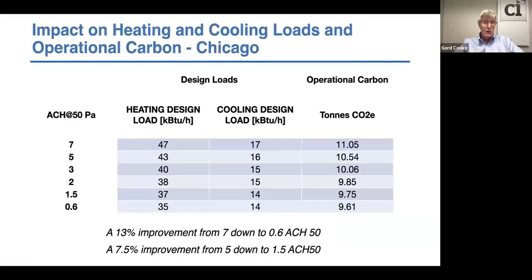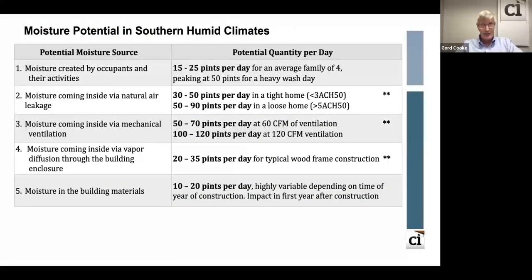But I'm just highlighting here the Chicago market, the design heat loads. When you go from, say, 3 air changes at 40,000 BTUs, that's on the left-hand side, down to 1.5, a small change in heating load reduction, and also a change in cooling loads. So nice little reductions in heating and cooling loads to help you rationalize those sizes. I wanted to show you the Houston context.